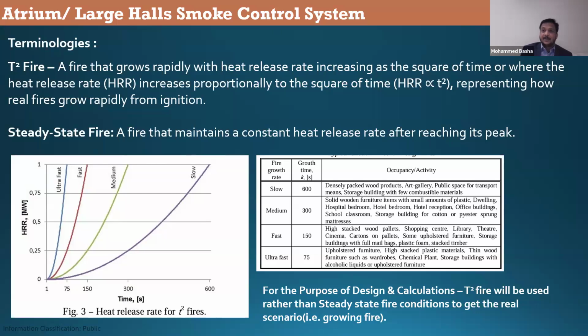from ignition. You know, when you have a car or a sofa burning, initially it will burn at one place, releasing 1 kilowatt of heat energy, let's assume. Then the fire starts to move further because of the next combustible materials, and it's burning and burning and burning. So at every second, the heat release rate will be varying, increasing. It's not decreasing or staying the same, it's varying. So when the heat release rate varies based on time, then it is called T-squared fire.